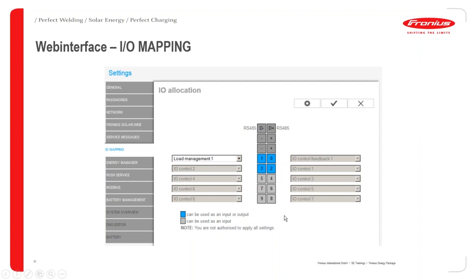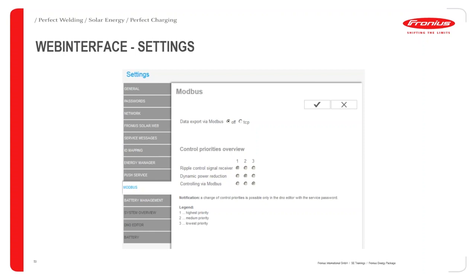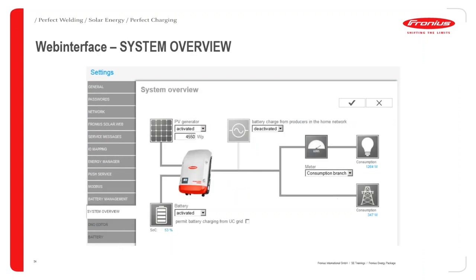So I/O mapping. In this case, this is more for looking into the future, introducing more functions for the Hybrid Manager. For example, when the Tesla comes out, you'll be mapping here for whichever you want to do. So, for example, one of the pins here will be mapped for the logic high-low. You've got the Modbus, and then other ones for +12, and there'll be some other triggering. For example, if you've got the emergency backup or the emergency power supply function, a couple of these will also be mapped for that. So, for example, your contactor auxiliary feedback and your relay contact to trigger the contactor. So this can be configured in lots of different ways. You can configure it also for ramping control, etc.